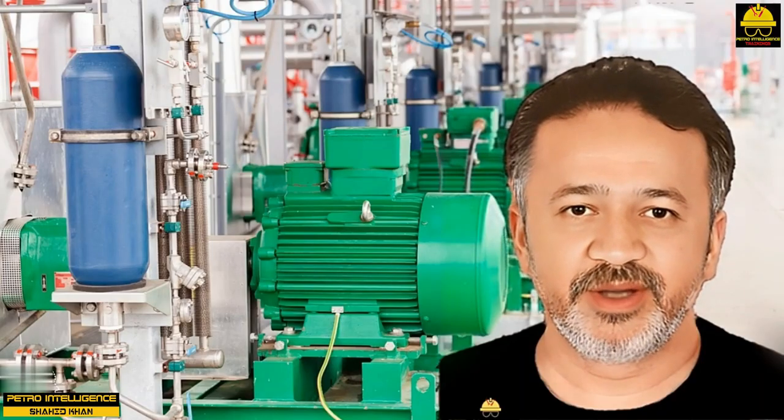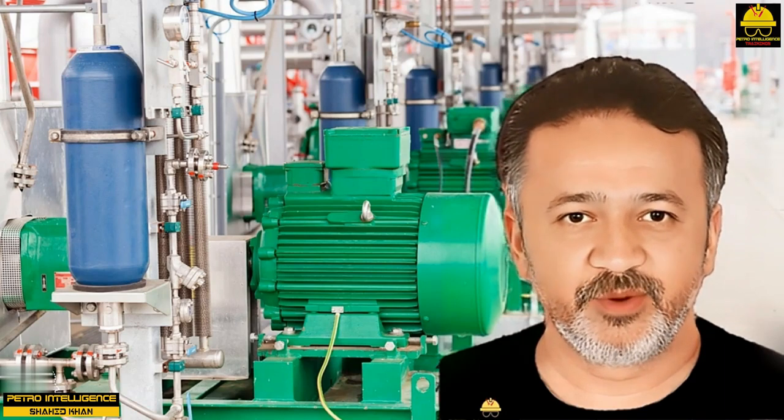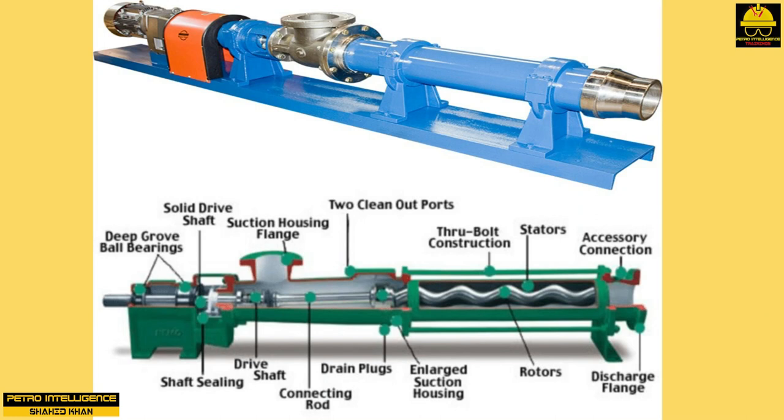Single screw rotary pumps or progressive cavity pumps. A progressive cavity, or PC, pump as shown in pictures consists of only one moving part, the rotor. The rotor turns inside an elastomer-lined stator. When the self-priming rotor turns, cavities, or voids, are formed between the rotor and the stator. These voids progress axially from the suction casing to the discharge outlet. During operation, the cavities fill with fluid.